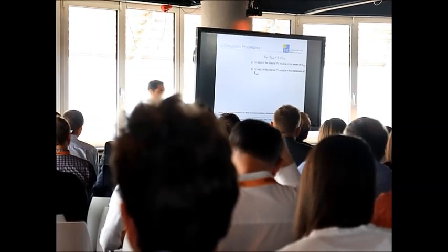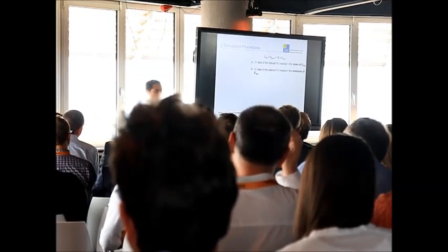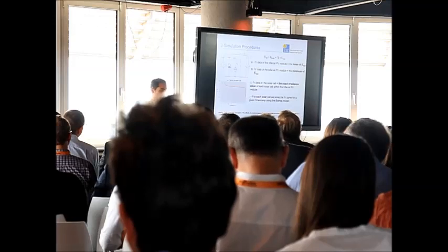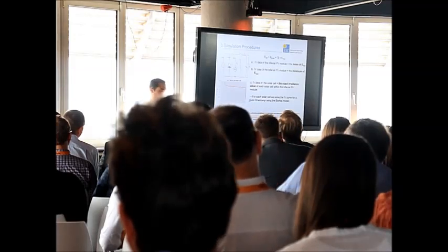So in order to solve this question of mean or minimum, I used 3 simulation procedures. The first one, I used the IV data of the bifacial module plus the mean value of the backside irradiance. And the second way, I used the minimum irradiance, also using the IV data of the module. And the third way, which I elaborated, I used IV data of the solar cell and the exact irradiance value of each solar cell within the 60-cell module.